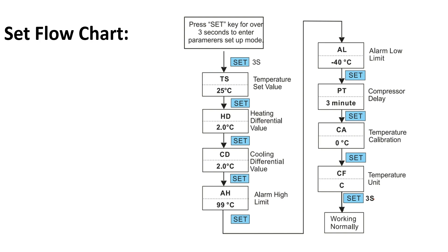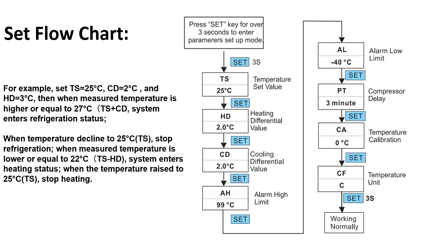Here we can see the significance of the HD and CD values. Suppose the user sets the temperature set value to 25°C, CD to 2°C, and HD to 3°C. When the measured temperature is higher than or equal to 27°C (which is the set temperature plus the cooling differential CD), the controller enters refrigeration mode. When the temperature declines back to 25°C, the controller stops refrigeration.